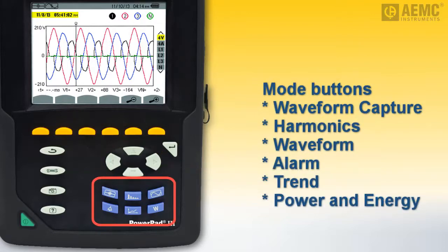Below these are six buttons for selecting the instrument's operational mode. Waveform capture mode enables you to display and capture transients and inrush events. Harmonics mode displays harmonic levels for voltage, current, and apparent power, order by order. Waveform mode displays current and voltage graphs, along with measured values and those calculated from voltages and currents. Alarm mode displays overages of programmable thresholds for a variety of parameters. Trend mode records changes to specified parameters. And power and energy mode displays power and energy measurements. The full use of these buttons is described in detail in the user manual.